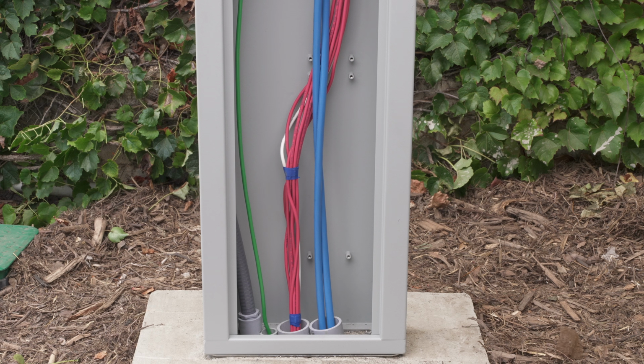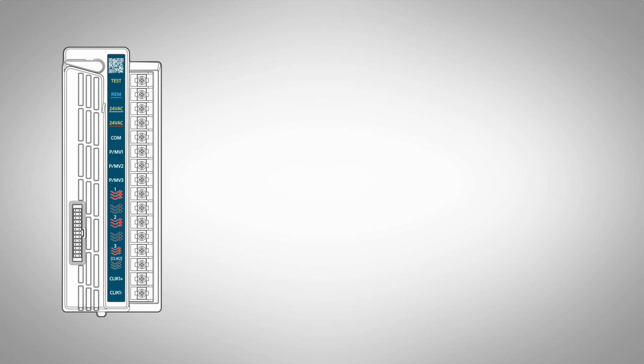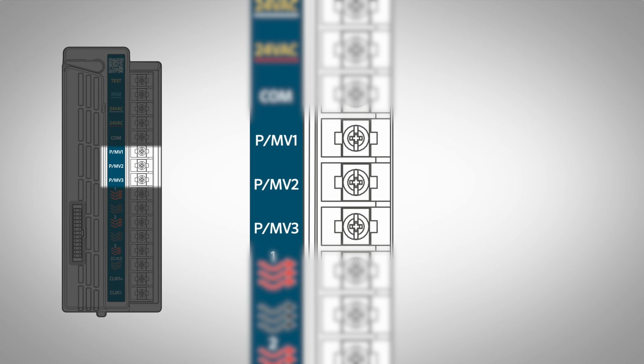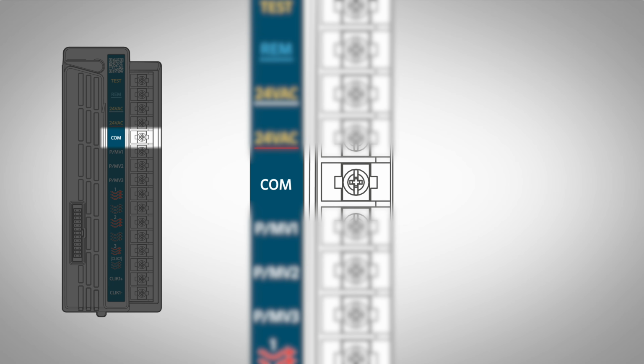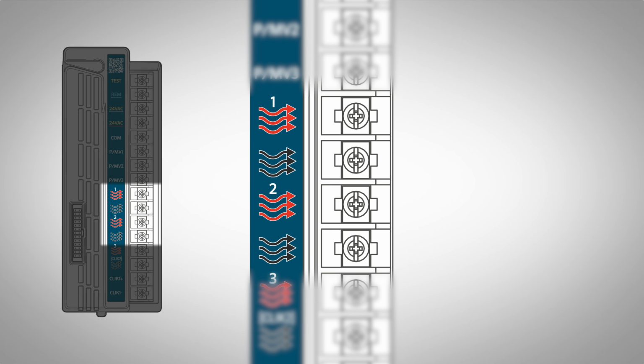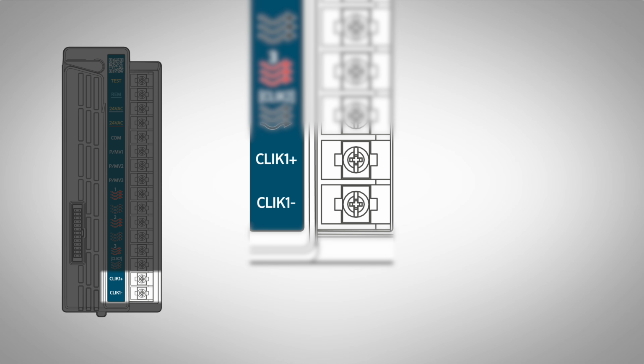Sensor wires should be installed in their own separate conduit and connected to relevant terminals on the controller's power module. There are 3 PMV outputs and a common terminal for the final connection. There are 2 flow sensor terminals, each with a red positive and a black negative connection. It's important to attach the wires from the sensor with the correct polarity, or they will not function. There is 1 click sensor input with 2 terminals for rain or other simple sensor inputs.